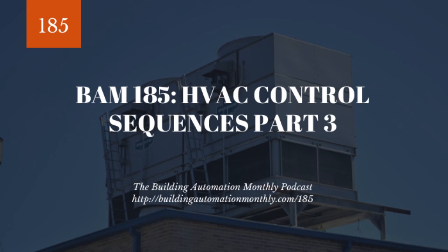When we're using variable air volume systems, that's where things get a little weird, and that's why we tend to have to use airflow stations in order to properly control. Anyone who's telling you that with a variable air volume air handler, just by putting 10% at the minimum outdoor air damper position, you're actually controlling to ASHRAE 62.1, is really not giving you proper information, because as you start to vary the speed of the air being drawn by those fans, you actually are affecting the amount of air that's going to be coming through those dampers and the mixture accordingly.